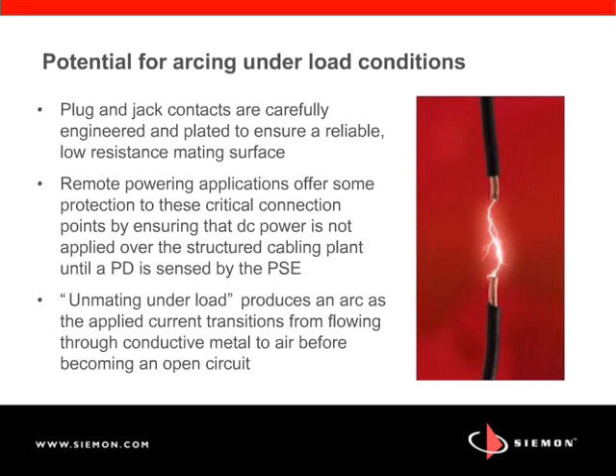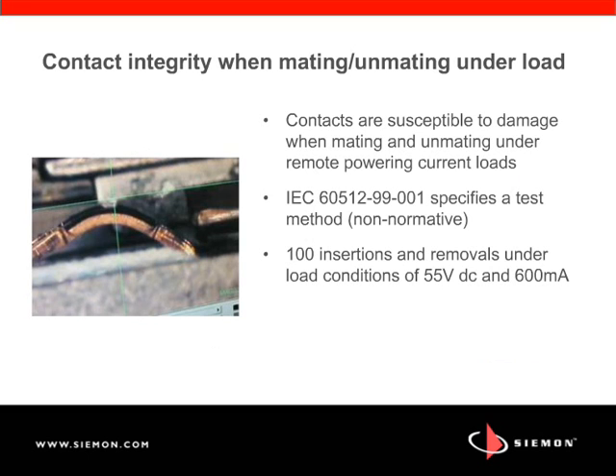Now, I want to emphasize that the current level associated with this arc poses absolutely no risk to humans. However, this arc does create an electrical breakdown of gases in the environment surrounding the contacts that potentially results in corrosion and pitting damage on the plated contact surface at that arcing location. So this is something we need to consider when specifying products to support high DC power currents of 30 watts and higher.